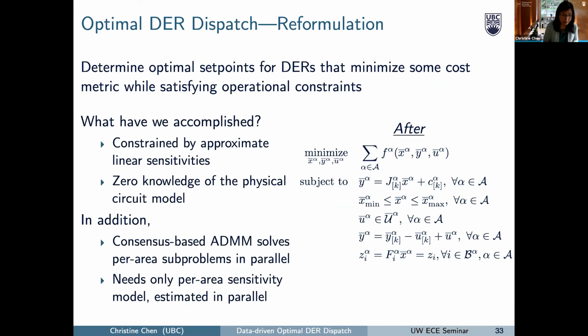So what have we accomplished? We're still dealing with the problem of determining optimal set points for DERs. As before, the problem is constrained by approximate linear sensitivities, requiring zero knowledge of the physical circuit model. Now we're able to solve per-area problems using consensus-based ADMM in parallel, and each subproblem only needs the per-area sensitivity model. The sensitivity models are also estimated in parallel, and the only requirement is communication between adjacent areas about the boundary buses.